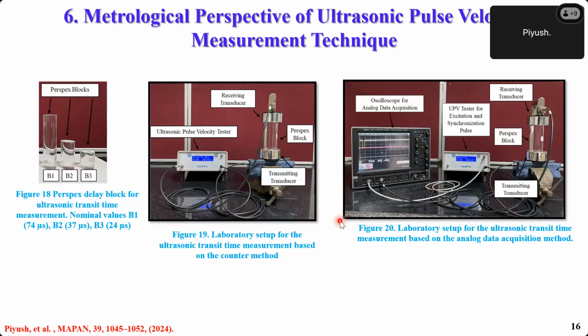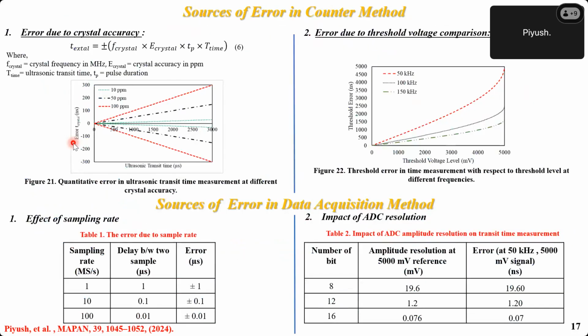Now I'm going to compare both instruments. What is the accuracy of these instruments? I'm going to measure the ultrasonic pulse velocity in these blocks. These are the perspex blocks, standard blocks. Now the counter method has two errors. The first is due to the crystal accuracy, and the second is the error due to threshold voltage comparison. I already explained the threshold voltage comparison, and every timer requires a crystal to measure the time. This crystal produces an error in the measurement, but we can reduce it by using a high accuracy crystal. Here you can see that a higher accuracy crystal produces a lower error in the measurement.